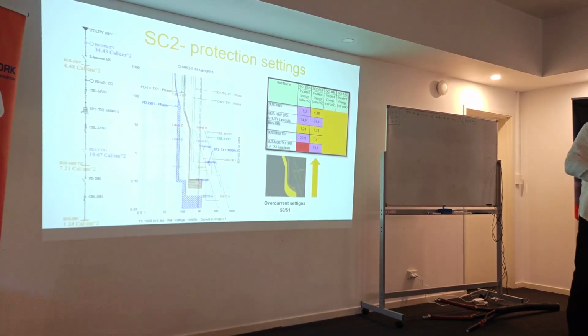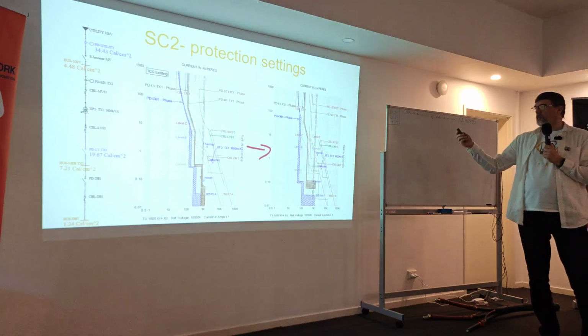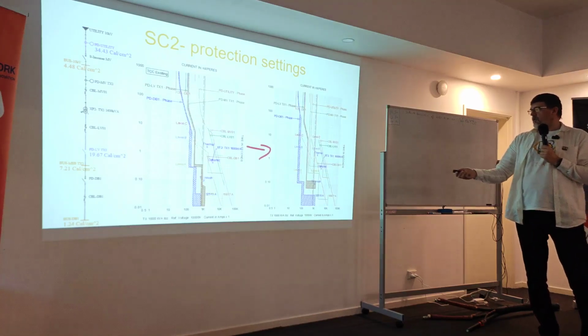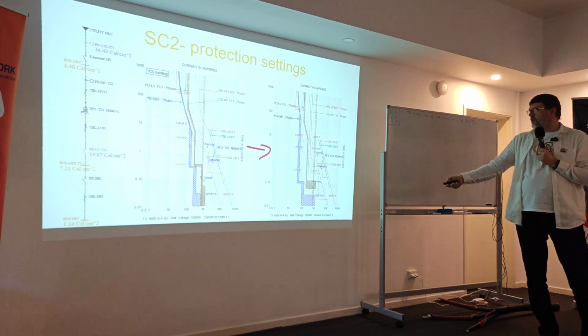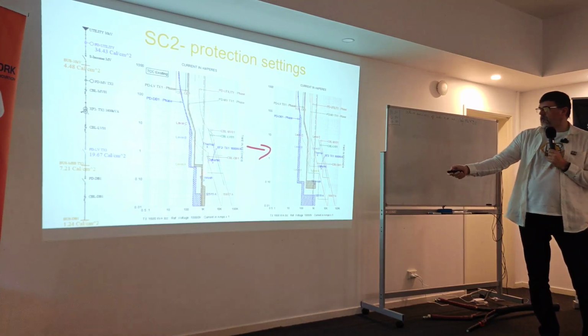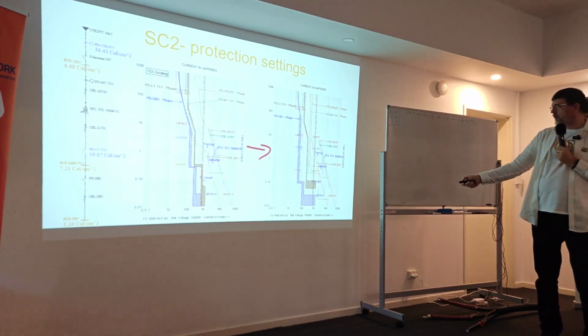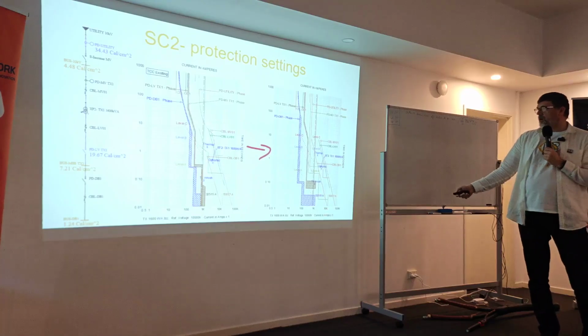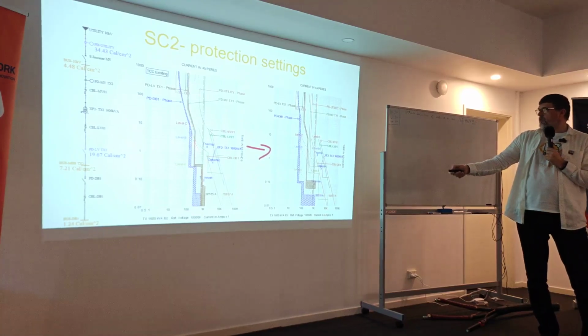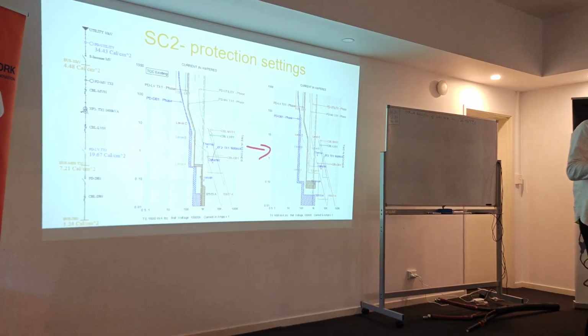And we also improve the way it works from the operation perspective. Yeah, that was the comparison if you want to see. The main thing was that the medium voltage was a bit higher for the transformer, so it can be much lower, and we don't have to use these inverse time curves. You increase the tripping time. No, I reduce, but I increase in this area. The separation between the curves is bigger.